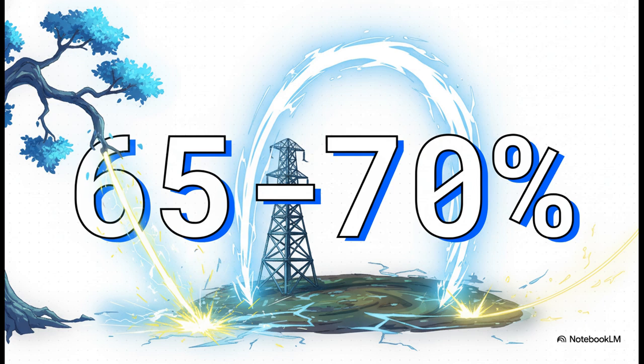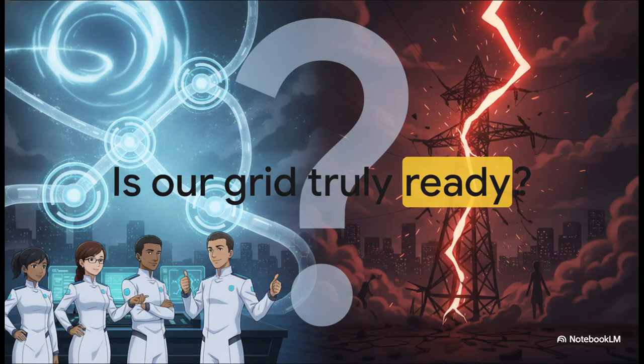Whether a tree branch falls on a wire or a ceramic insulator cracks and lets the current arc to the metal tower, this single, unbalanced connection to the Earth makes up the vast majority of every grid disruption we ever experience. You know, it's honestly a miracle of modern engineering that we can automatically detect, isolate, and survive thousands of these ground faults every single day without the whole electrical system collapsing. We are absolute experts at surviving that 70%.